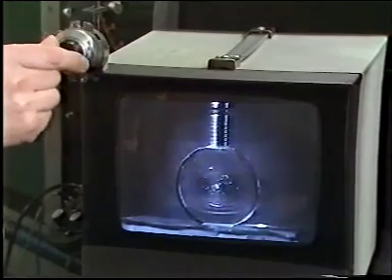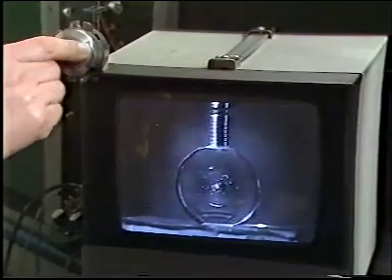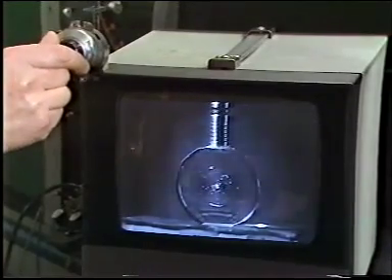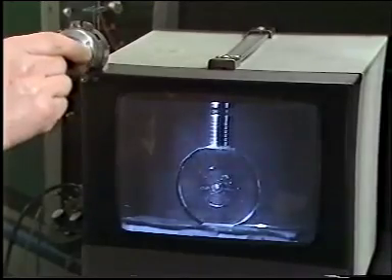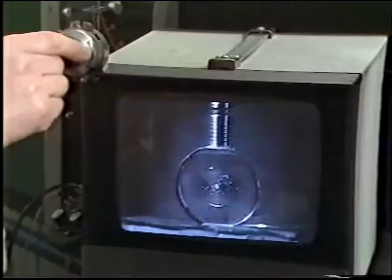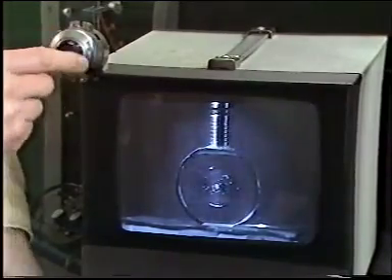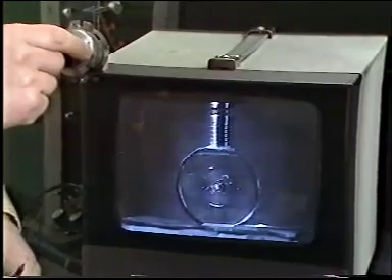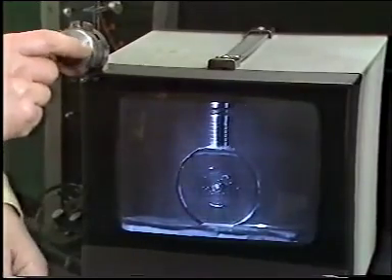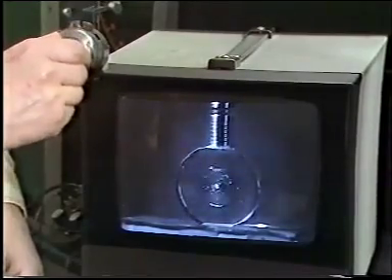I go right down to the bottom of the block, and now you can see the wave bouncing off the bottom. It reflects from the bottom and comes back up to the top as we put in more and more delay, until finally I can see the wave hitting the transducer again. Now, it's this situation which is commonly used in flaw detection for looking for defects in opaque materials. So I'll wind this back to there.